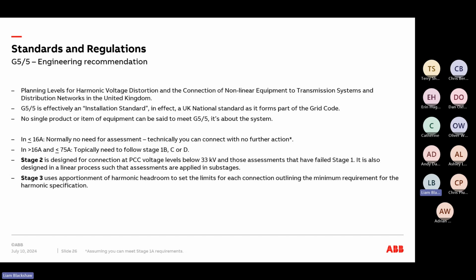We're not looking at individual components or individual parts of the installation or the network. We're going back to where that point of common coupling is, the PCC. And that's where we measure our harmonic content. And that's where we say, depending on the stage or criteria, that's what limits we need to adhere to.